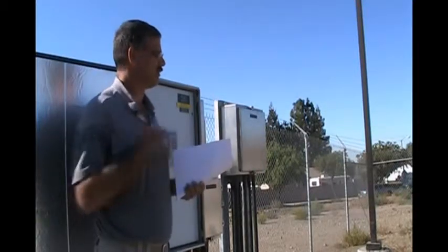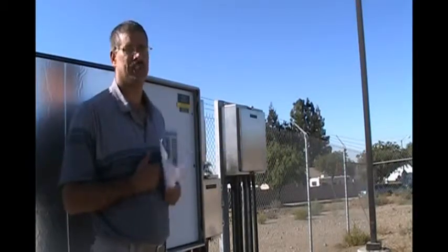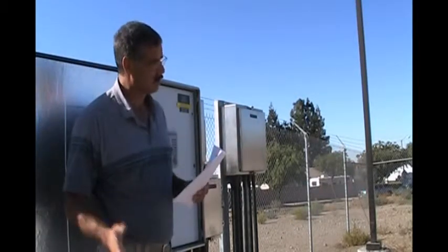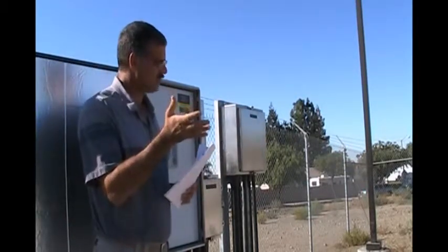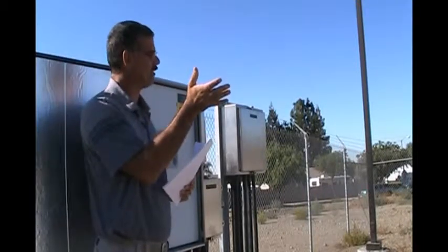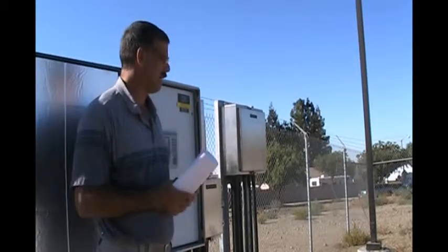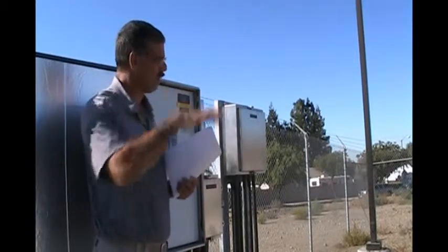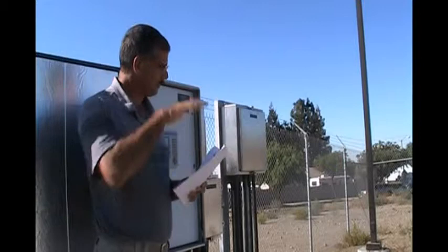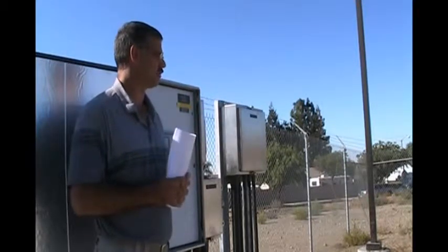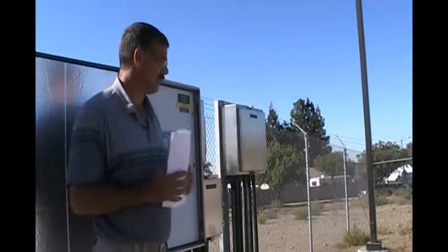Okay, so for instance, if I type in I want it to go to 50%, it's not going to just shoot to 50%. It's going to bring it up about halfway, let it settle and stable because there'll be some overshoot, and then it'll go halfway again between that point and the target, and it'll inch its way in nice and easy, nice and gently, so we don't have any water hammers or quick shut-offs or anything like that, erratic changes in pressure. And this is really kind of important when it shuts off and it's going to 0, that we kind of inch in, okay, into the closed position. So we've taken that into account. And you saw today they were putting on some speed control valves to also make sure that that operates as required.